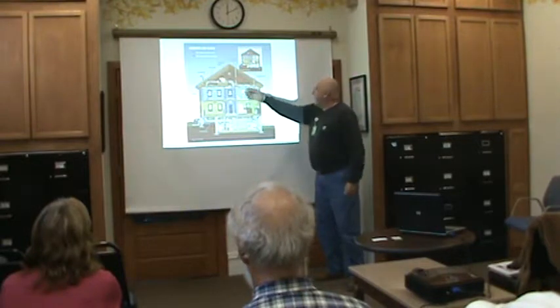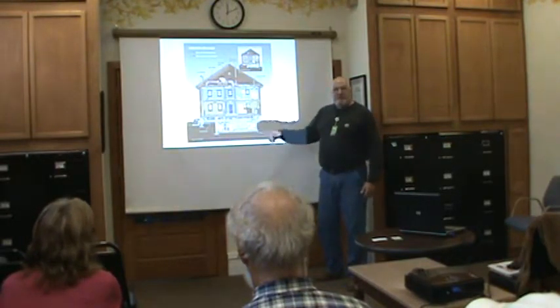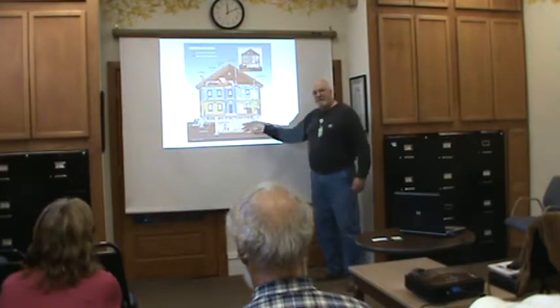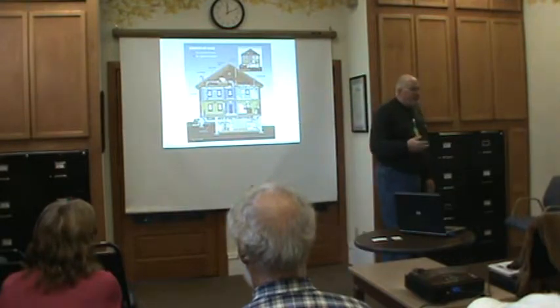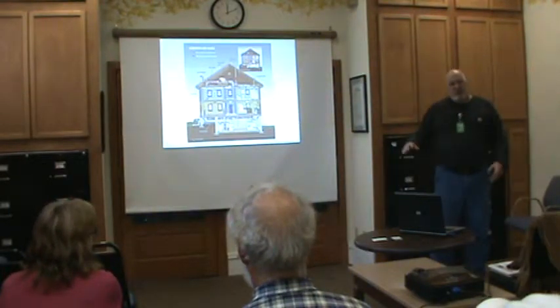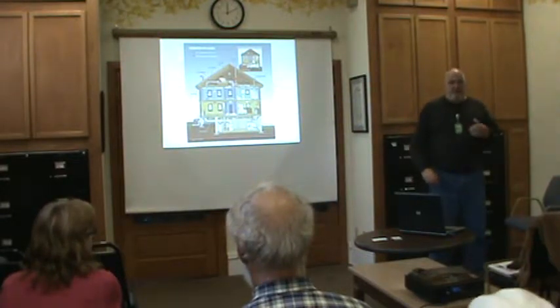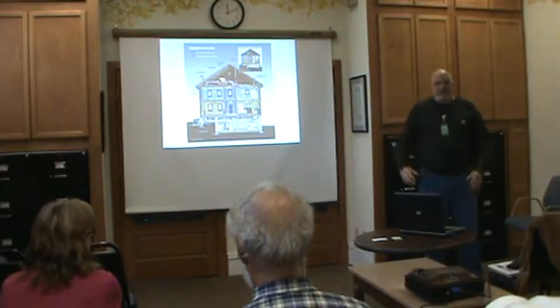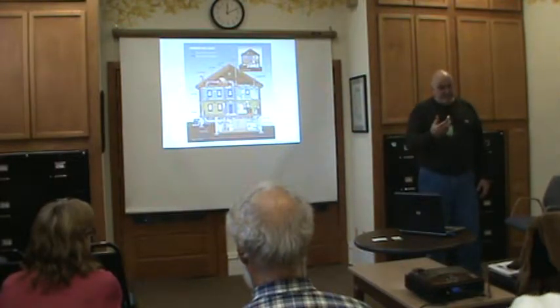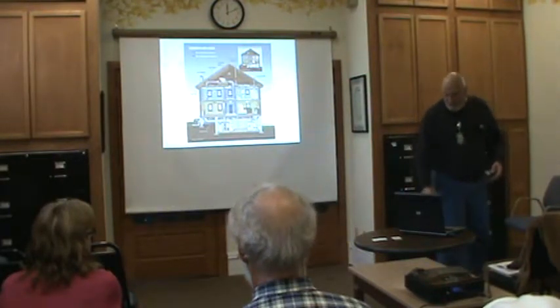In the stack effect, when that hot air is coming up, there's a pressure differential, right? Where's the makeup air coming in? Well, it's the cold air coming in through every crack and crevice in the basement. And that's how you end up with a drafty, uncomfortable house. So all that fresh air coming in, as it were, is unfiltered. And when you build a super tight house and you figure out I'm going to manage my ventilation with filtered ventilation, that's when you see really great advancements in the indoor air quality.